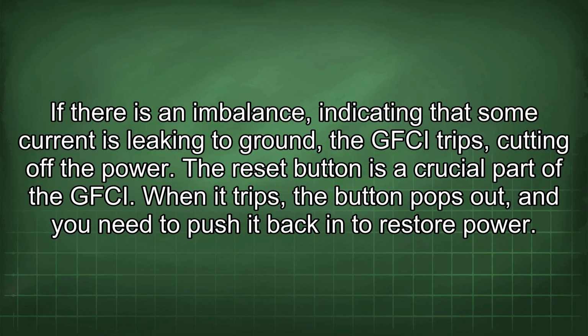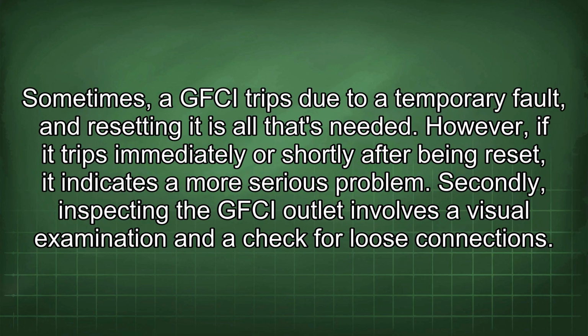The reset button is a crucial part of the GFCI. When it trips, the button pops out and you need to push it back in to restore power. Sometimes a GFCI trips due to a temporary fault and resetting it is all that's needed. However, if it trips immediately or shortly after being reset, it indicates a more serious problem.